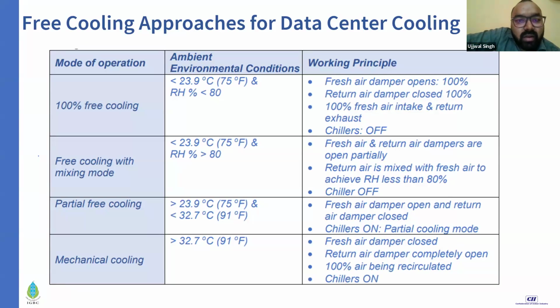In free cooling, they have defined various modes for when 100% free cooling will be operated. In this specific case, 100% free cooling will be operated when ambient temperatures are lower than 23.9 degrees Celsius and RH is less than 80%. They calculated these thresholds based on the environmental conditions prevailing over Bangalore for the year, and calculated their free cooling hours, which we are also going to do now.